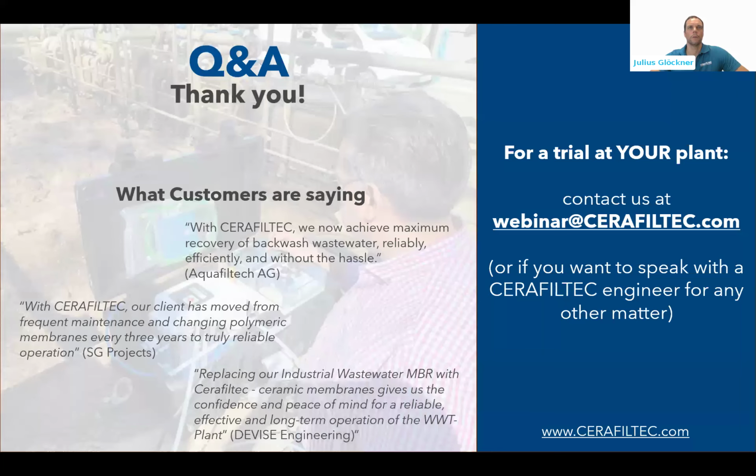What was your water recovery percent in the normal desalination stage, so pre-treatment? What's your water recovery, and what is your salt rejection and energy use? Okay, so the recovery in seawater also depends a bit on where the intake is located and so on. But generally speaking, we always reach more than 95% recovery rate in a seawater application without further pre-treatment like clarifier or dissolved air flotation.